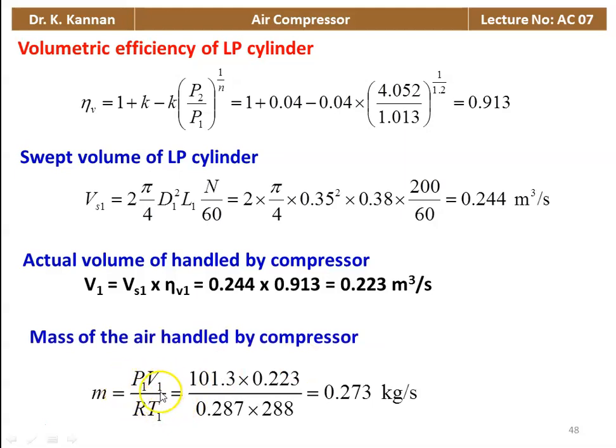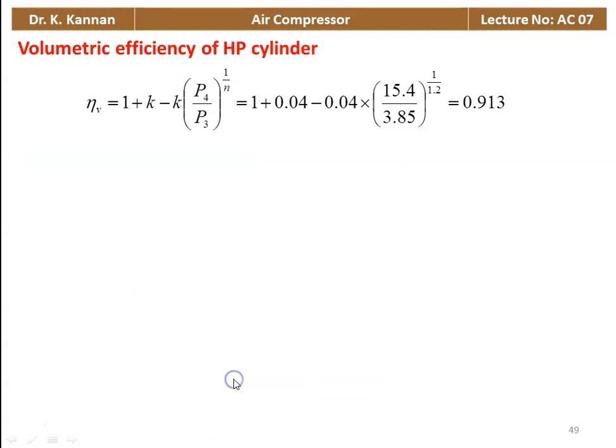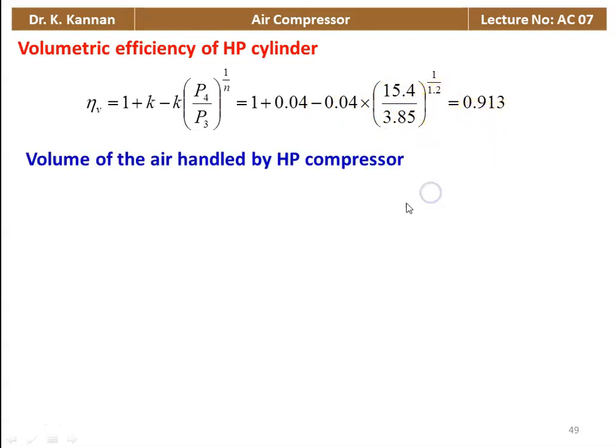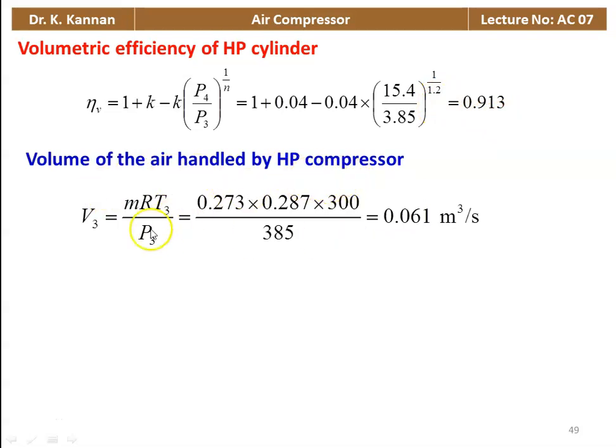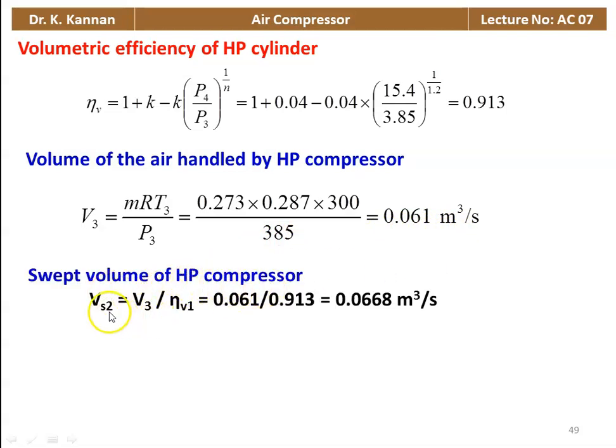Mass of air handled: M = P1V1 / RT1 = (101.3 × 0.223) / (0.287 × 288) = 0.273 kg/s. Volumetric efficiency of the HP cylinder: η_V = 1 + K − K × (P4/P3)^(1/n) = 1 + 0.04 − 0.04 × (15.4/3.85)^(1/1.2) = 0.913. Volume of air handled by HP compressor: V3 = MRT3/P3 = (0.273 × 0.287 × 300) / 385 = 0.061 m³/s.